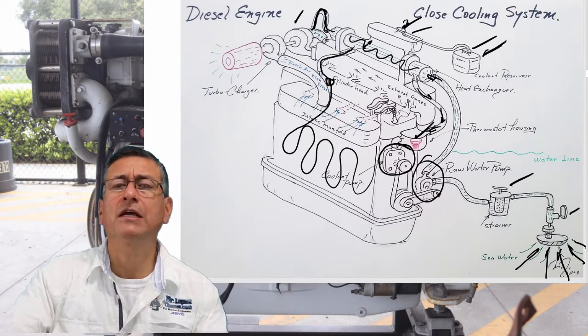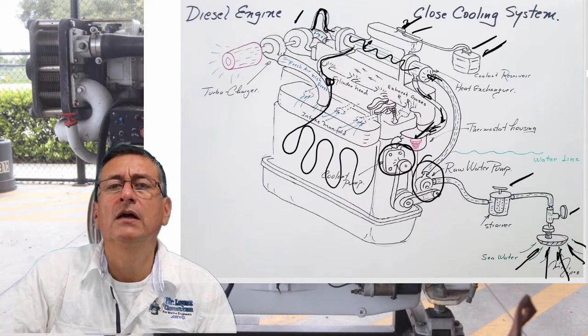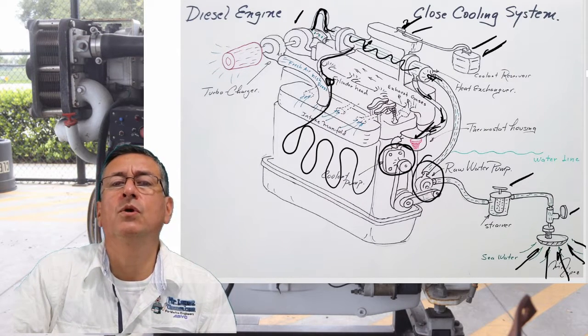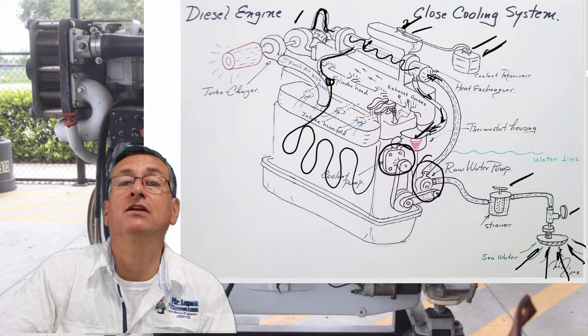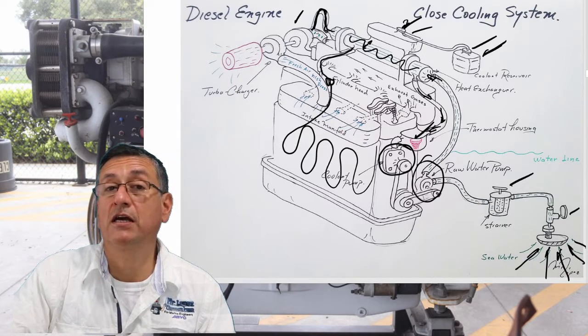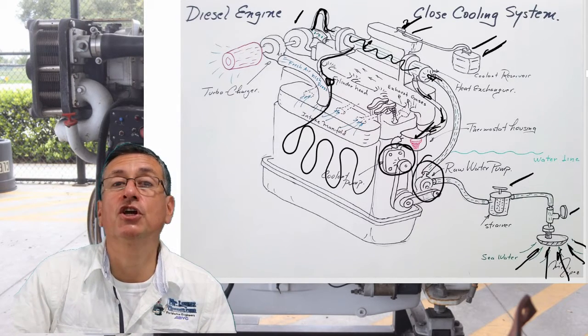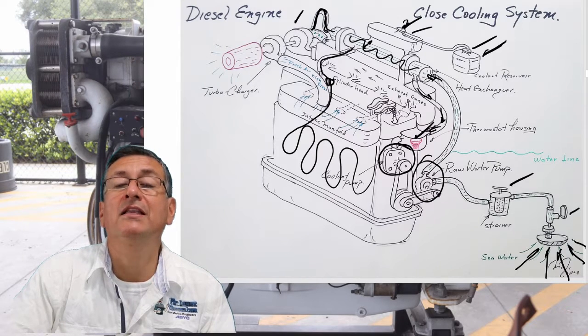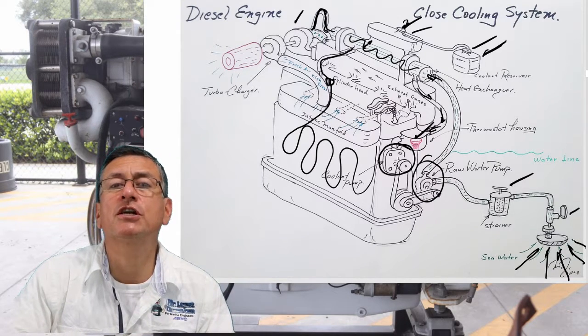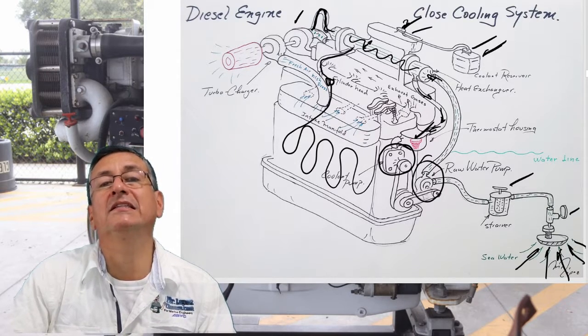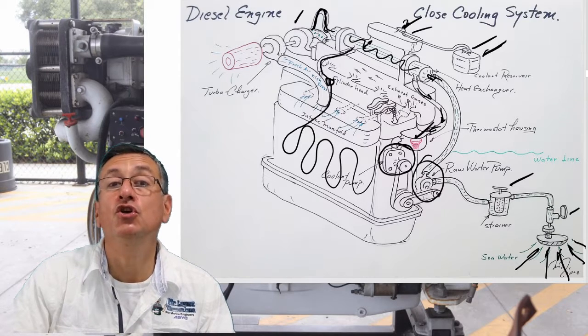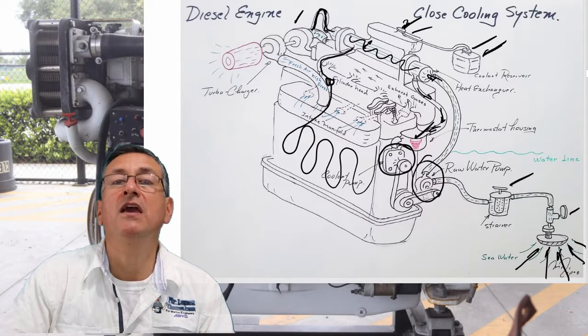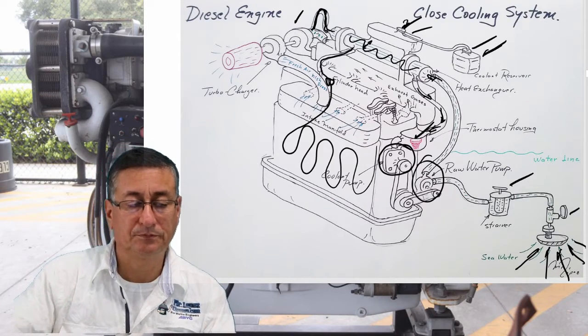What is the recommendation? Send the heat exchanger to a special shop dedicated to checking radiators and heat exchangers. They pressurize the heat exchanger and verify if it is cracked internally. This is the technique used to verify if the heat exchanger is broken internally.